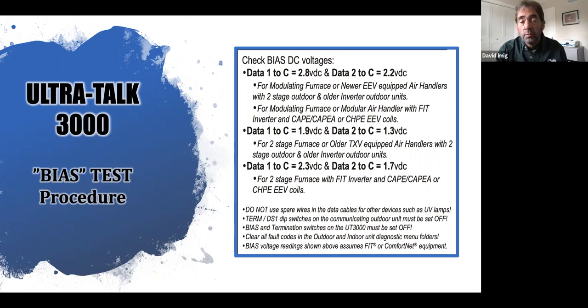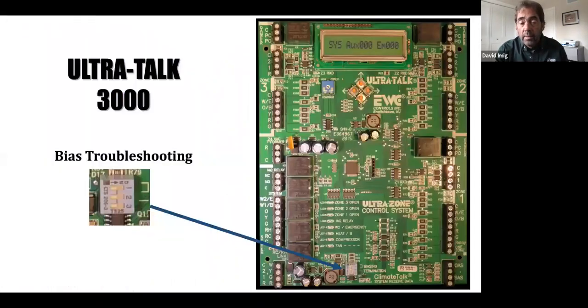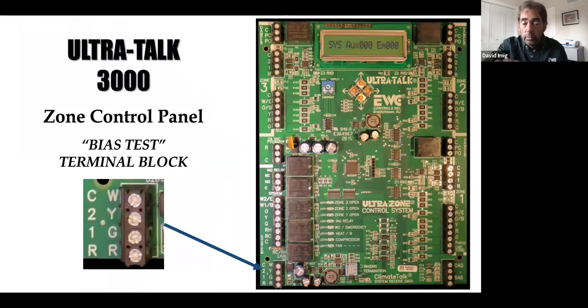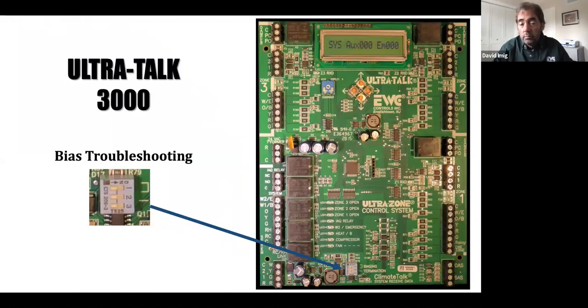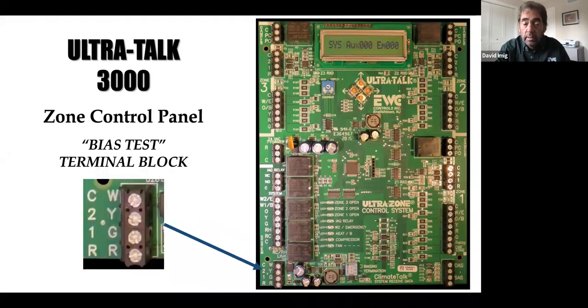And if you don't do it on the immediate fire up, you'll eventually do it and find that somewhere in that wiring, part of my installation is not done properly. That is all done in this location, where you're going to do all that testing. The bias is where I look to make sure. And that's all you're doing with this particular dip switch block: making sure that all of these switches are to the left. They all need to be off. All the switches on the bias block on the outside unit need to be off. That's the way they should come from the factory. They should be checked to make sure they didn't get put in the wrong position or bumped in some fashion so that one or more of them might be in the on position. I do my bias testing here. Everything checks out. I'm good to go.